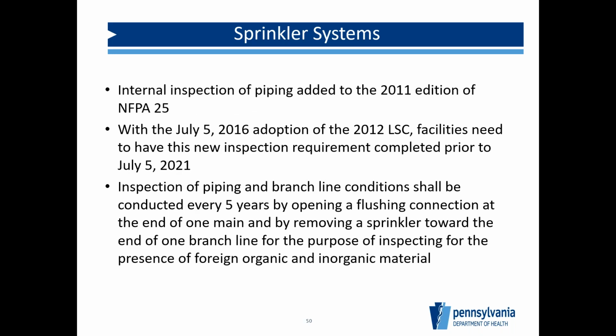So this one we have a little bit of time yet. With the July 5th, 2016 adoption of the 2012 Life Safety Code, NFPA 101, there's a new inspection requirement in NFPA 25, which is the requirements for sprinkler system inspection and testing. There's a new internal inspection of piping that was added, but it gave 5 years for facilities to do it. So you have to do this every 5 years. So we have till July 5th, 2021.